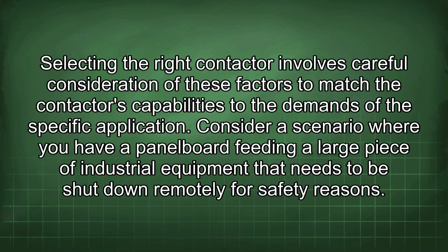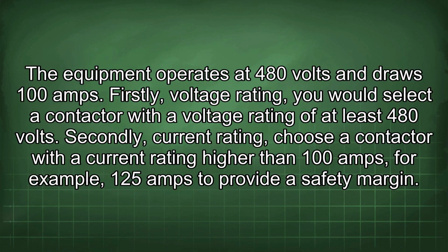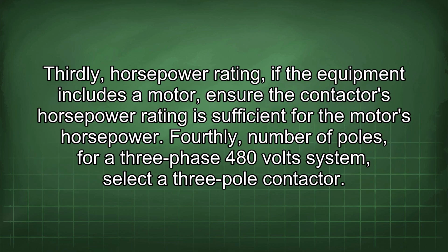specific application. Consider a scenario where you have a panelboard feeding a large piece of industrial equipment that needs to be shut down remotely for safety reasons. The equipment operates at 480 volts and draws 100 amps. Firstly, voltage rating. You would select a contactor with a voltage rating of at least 480 volts. Secondly, current rating. Choose a contactor with a current rating higher than 100 amps, for example, 125 amps to provide a safety margin. Thirdly, horsepower rating.